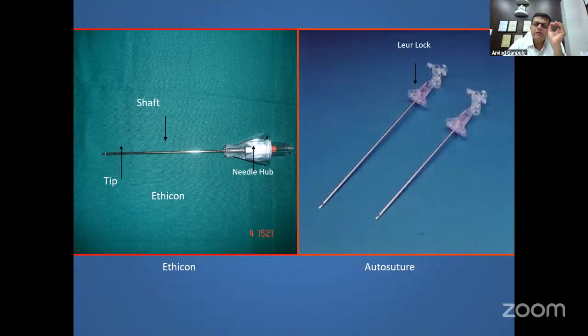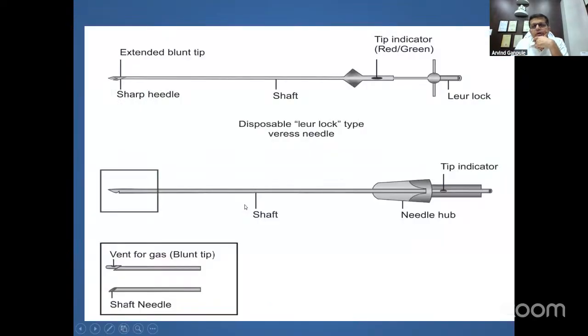The indicator, which is marked with the arrow here, if you are in the proper position, the Ethicon needle will always show a green indicator. If you are in the preperitoneal space, it will be red, otherwise it will always be green. These safety specifications you will never see in reusable ones, and I feel that is the biggest problem. The hub is not transparent in reusable ones. We'll go into a bit of detail of this.